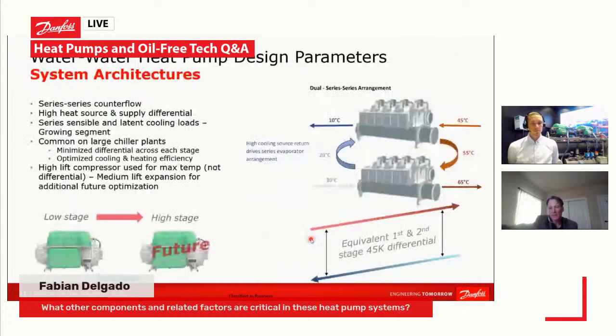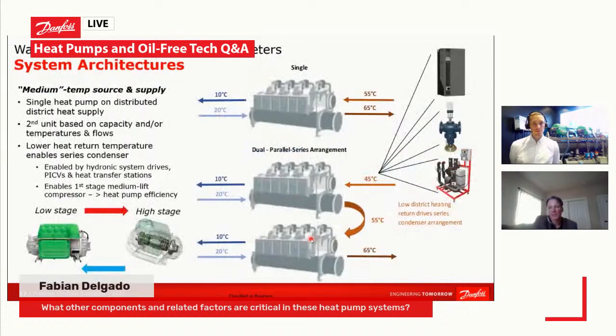With the ultimate system shown on the next slide, the series counterflow cascade that I showed earlier as well. But to answer the question, how you enable that lower district heating return water temperature is on the demand side, the building side. This is the supply side, right? Because we're supplying the heating to the district heating system. And this is the exact same phenomenon that you see in cooling applications: every chiller is a heat pump, every heat pump's a chiller, and getting that mindset is critical, because the same factors apply on the heating as well as the cooling, especially as you electrify the heating. And that is specifically enabling the benefits of the variable speed drive that you're implementing on that heating system, on the hydronic system.